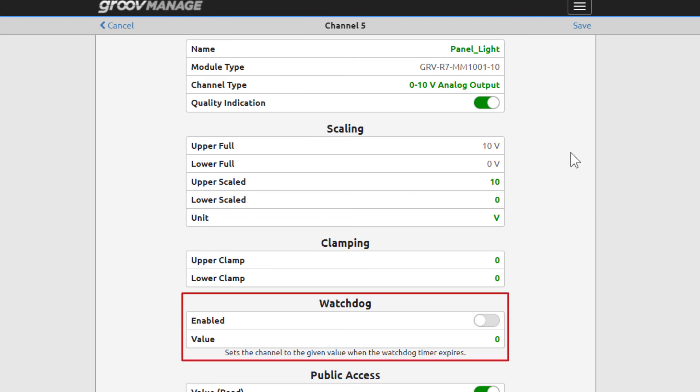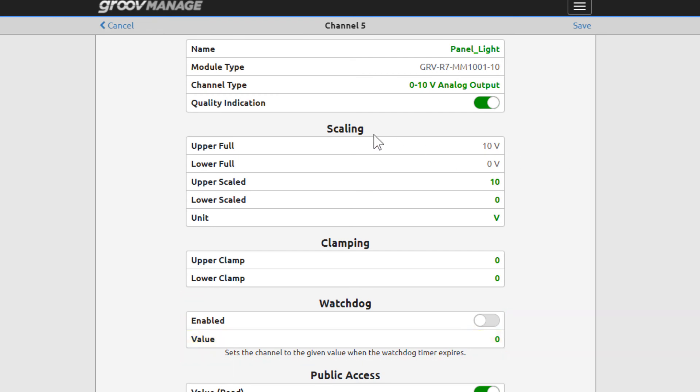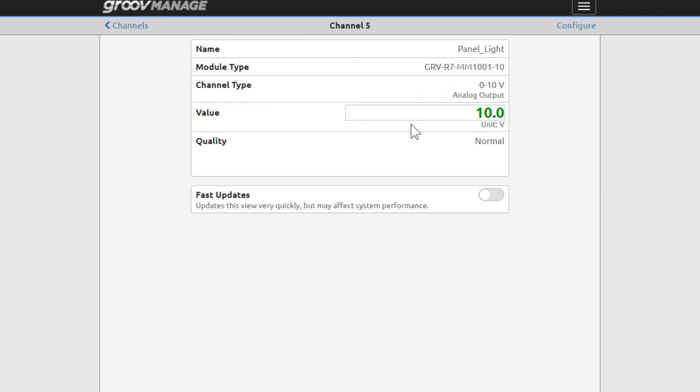Clamping lets you set a safe upper and lower limit for the output. A watchdog monitors communication from a host, like from a groov EPIC controller, on groov RIO's port 2001. If nothing has accessed the port in the time specified, then this channel goes to the value configured here. Its purpose is to automatically bring the process to a safe state should communication to the GrooveRio fail. Let's cancel from here and click Channels.